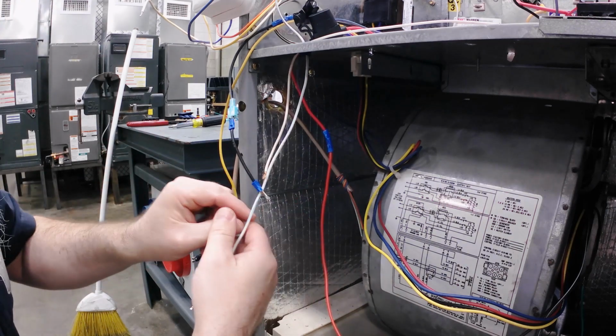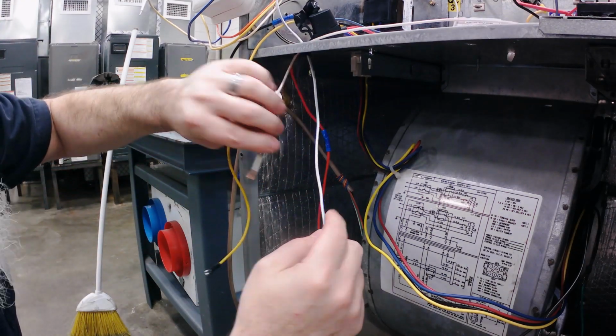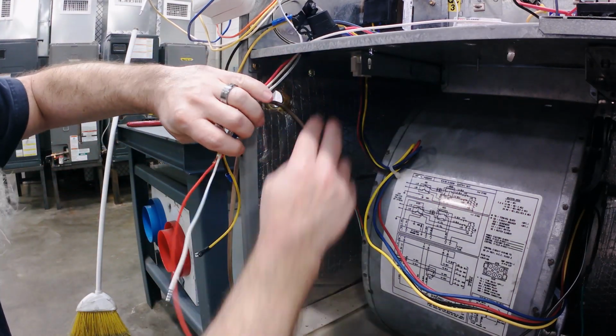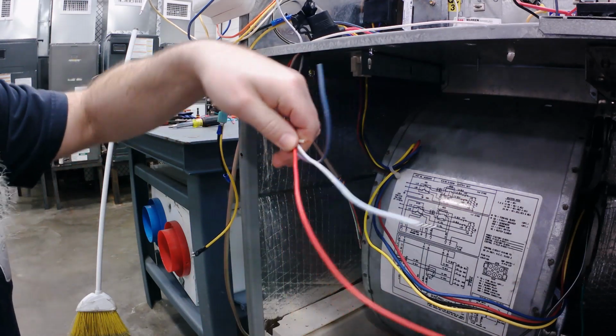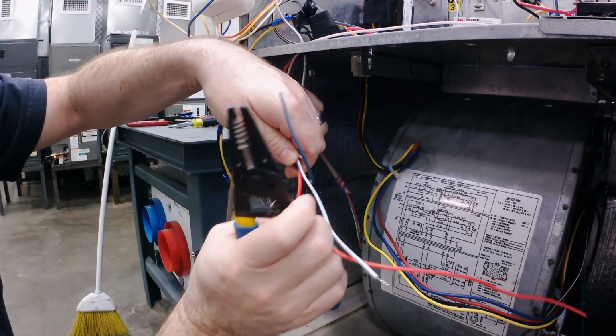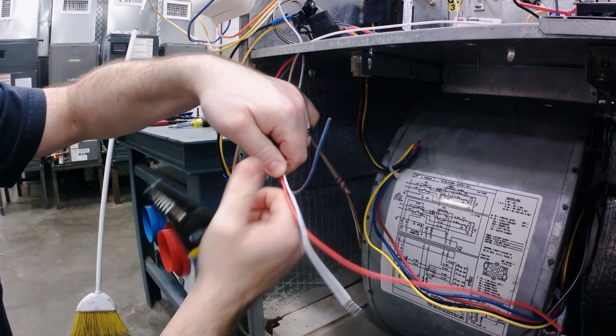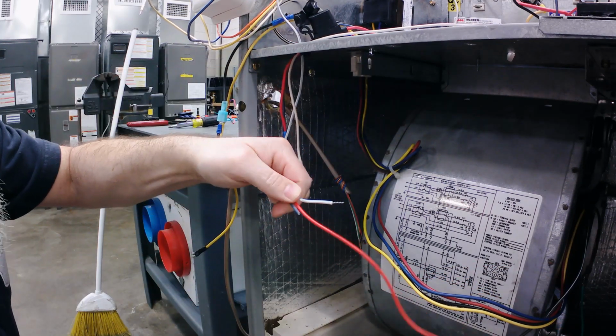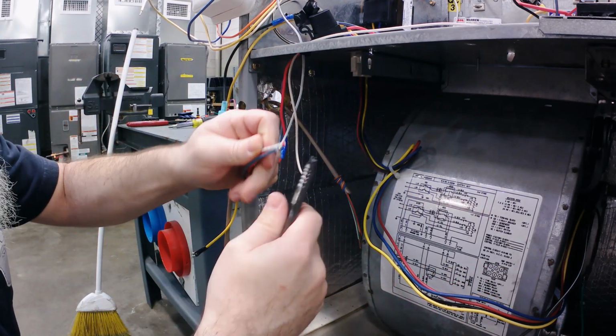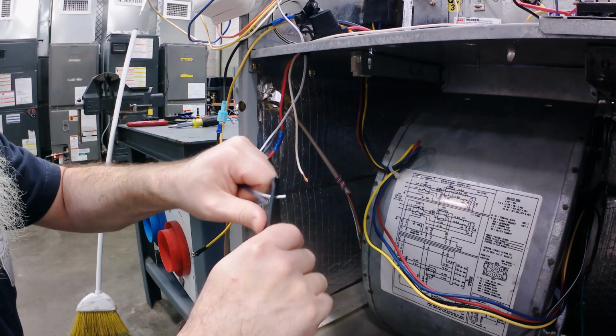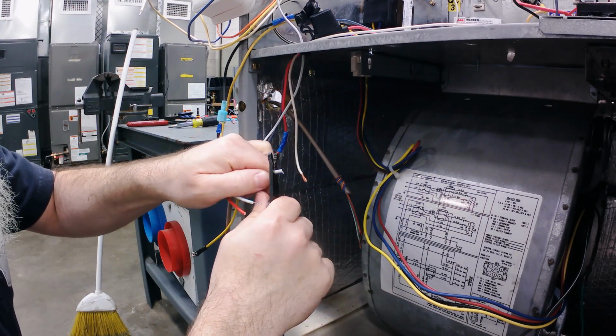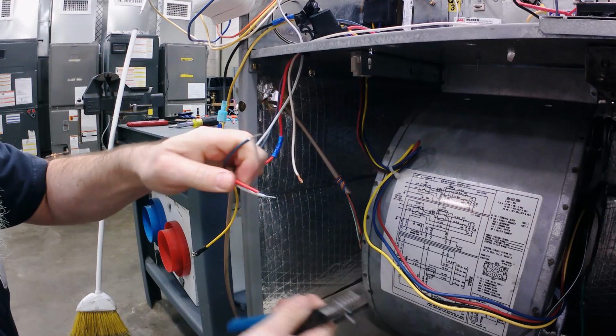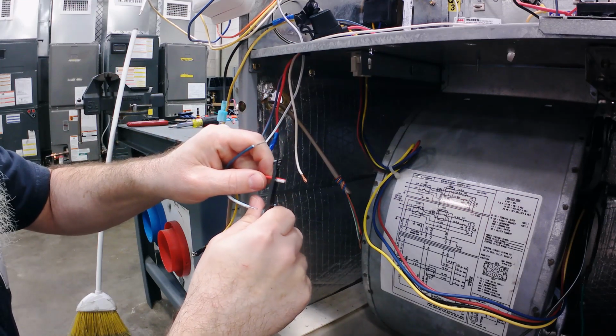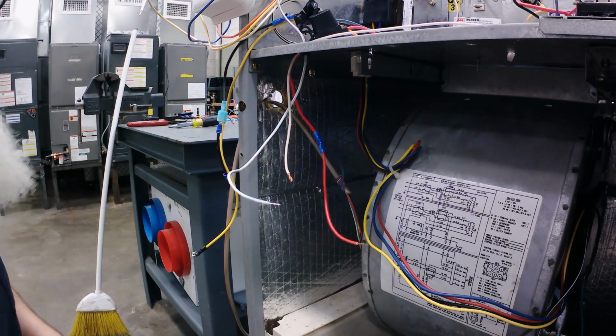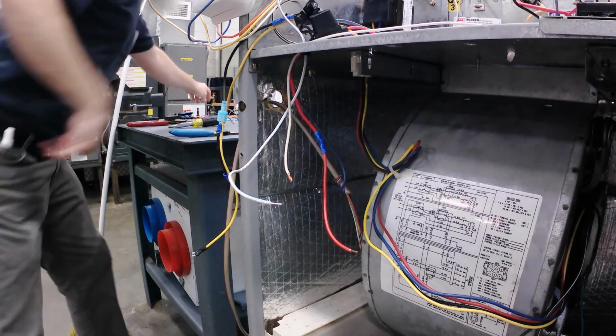I'm going to take my 24 volt connection, my white connection, my red connection, and my common, and try to keep them all about the same length. The white one's a little short, so we'll trim it right here, even with the commons, then pull all that off so we can make our low voltage connections to the thermostat at the corner of the screen.